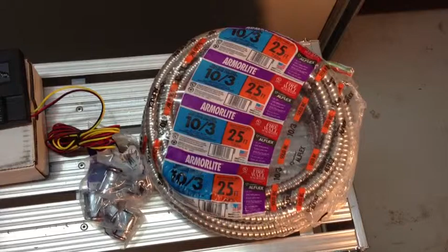Most of what we've talked about has been on the DC side, but next I picked up this cable today. This is a 10-3 cable with a ground, and I need to run a 30 amp breaker in my main house panel and run wires that will carry 30 amps over into this switch panel. These wires will run from the main AC panel, the house entrance panel, and come over into these 3 spots, the incoming spots into the panel, and into the ground bar, the green ground, the earth ground.